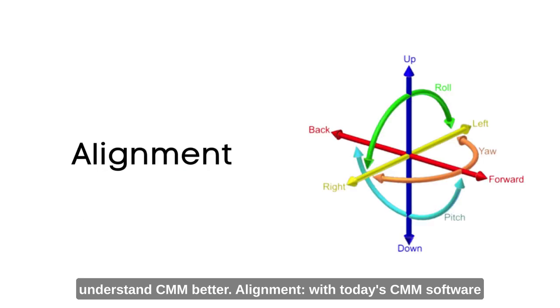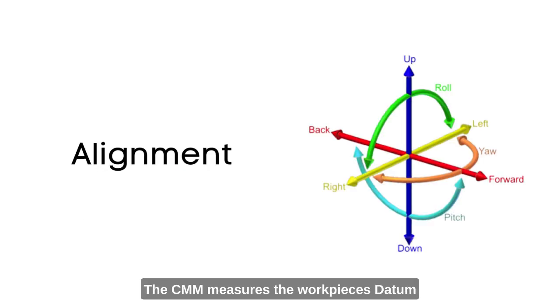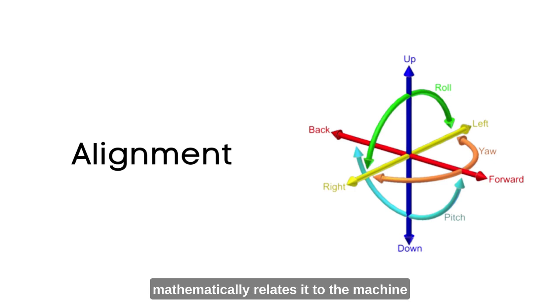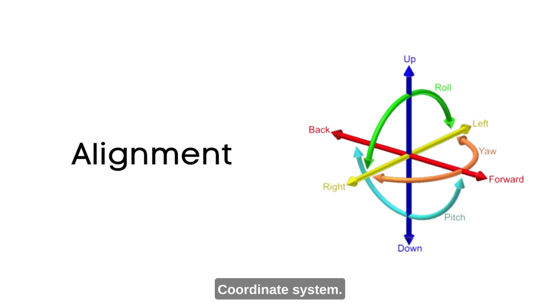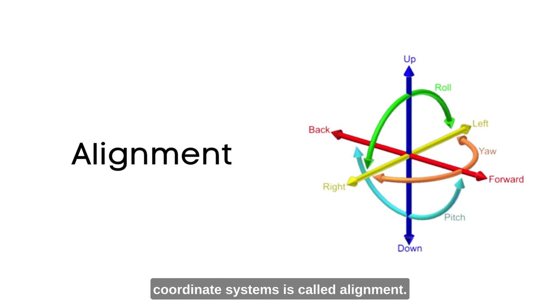Alignment: With today's CMM software, the CMM measures the workpiece's datums, establishes the part coordinate system, and mathematically relates it to the machine coordinate system. The process of relating the two coordinate systems is called alignment.